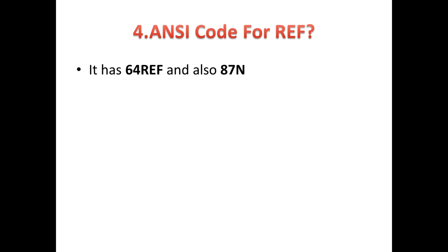Fourth question: what is the ANSI code for REF? Since its protection is similar to earth fault and also differential, we can use 64 REF or 87N. The commonly used ANSI code is 64 REF, and in some cases they also use 87N.